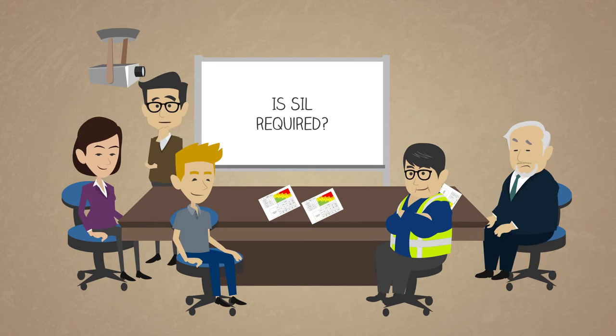Unless there's another layer of protection, it will need to be at least 99% reliable, or have a probability of failure on demand of less than 1%, which means it will need to be a SIL-2 rated system.